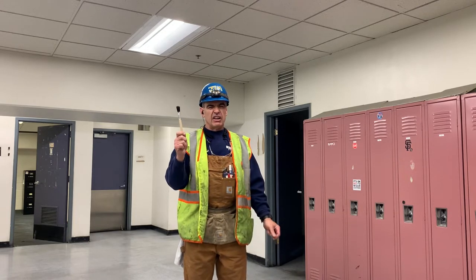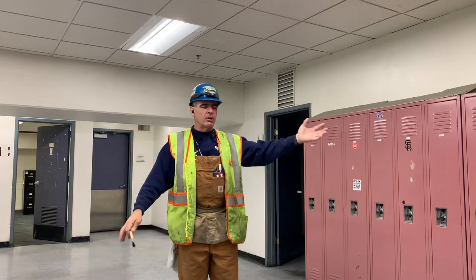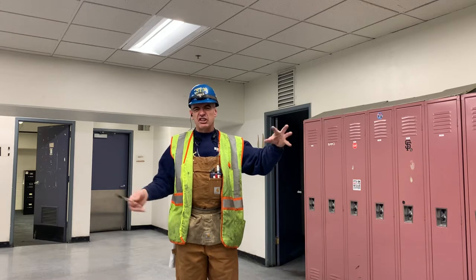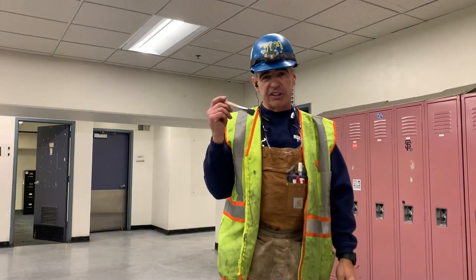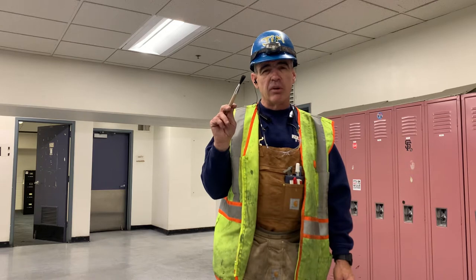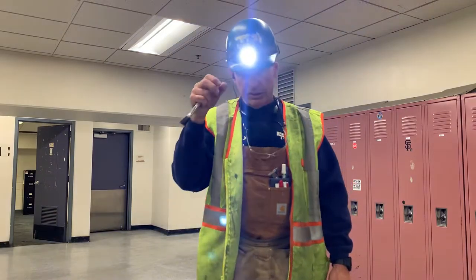Well howdy ho, good neighbor. Today we're cleaning loaded heads — that's right, fire sprinkler heads. After they've been in an area for a long time, especially next to duct registers where the air is blowing, they get loaded — that means dusty and dirty — and they might not work. So what we do when they're dusty or dirty is we'll take a little brush and very carefully dust them off. The loaded head will become a lot cleaner and we'll be able to inspect it better. Let's turn on the flashlight and I'll show you exactly what I'm talking about.